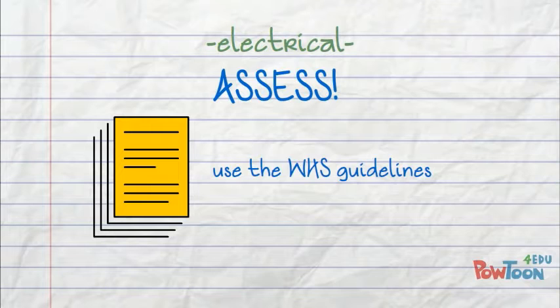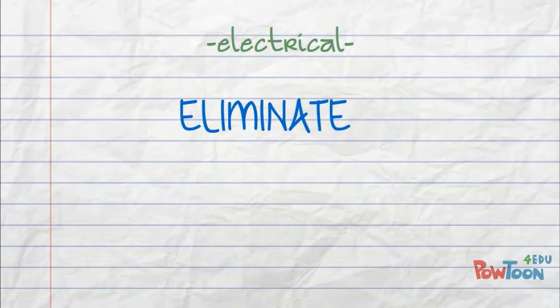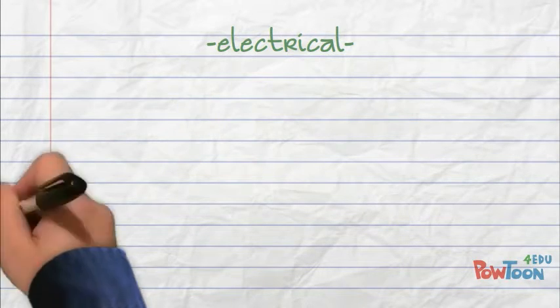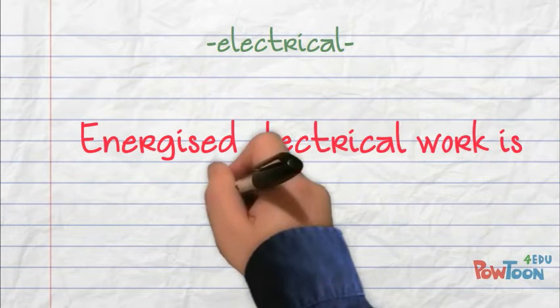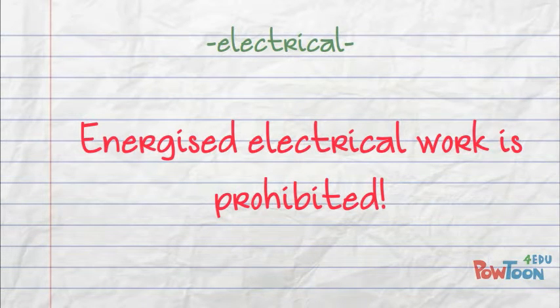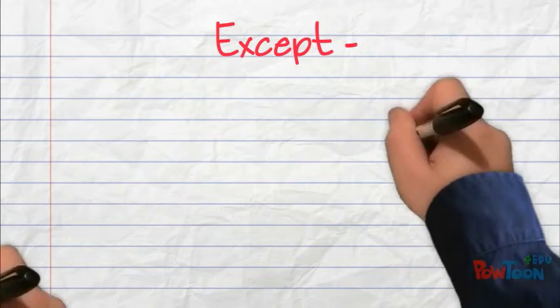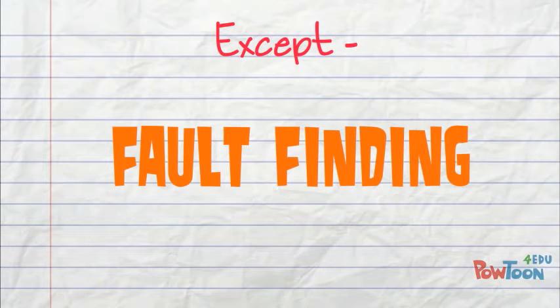There are different approaches to working on low voltage and high voltage equipment, and both require implementation of safe systems of work. The first control measure is to eliminate the need to work on live equipment. This includes isolating the equipment from the source of supply. WHS regulations prohibit energised electrical work, subject to certain exceptions. For example, when fault finding, it's necessary that electrical equipment to be worked on is energised in order for work to be carried out properly.